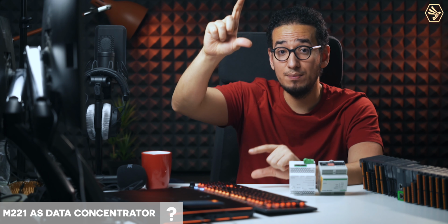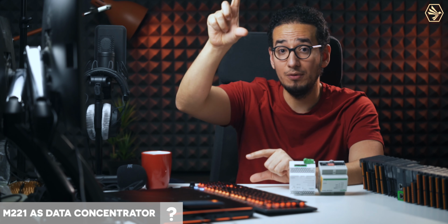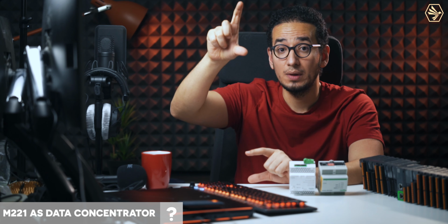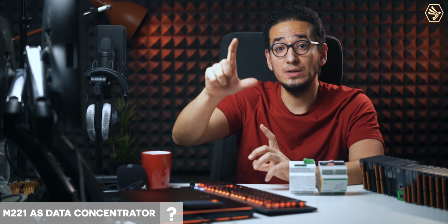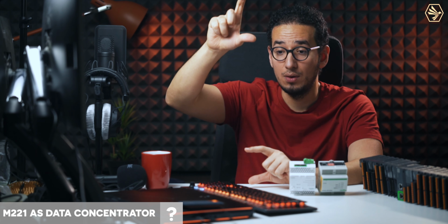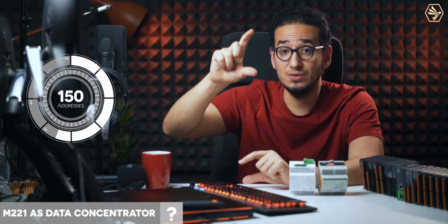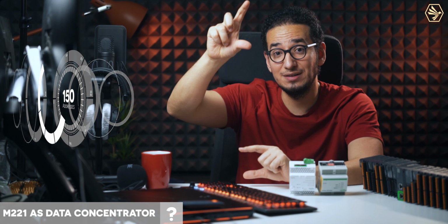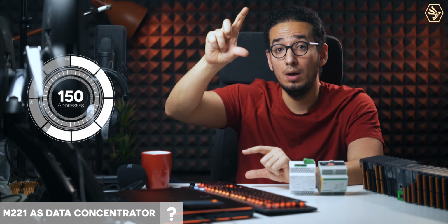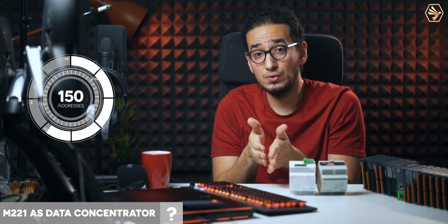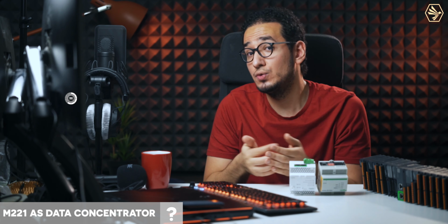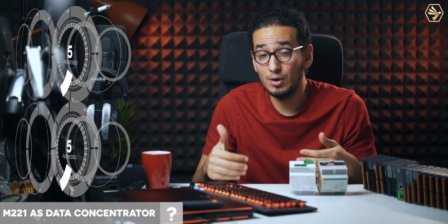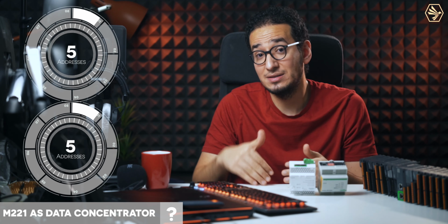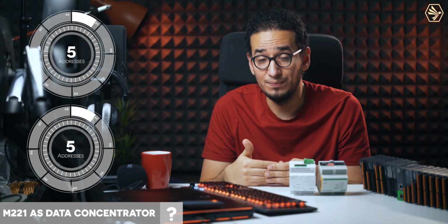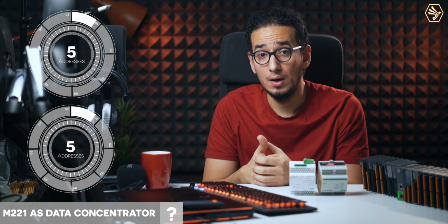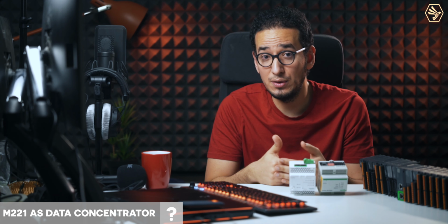So there is a huge gap between the data I need at the top of the stack and at the bottom. So here are two situations. Either you read 150 addresses just to get 5 addresses at the top and 5 addresses at the bottom, or you have to use 2 function blocks or 2 scanner lines. And the problem here is each scanner line creates a TCP connection, which creates a load on the master PLC and the network as well.